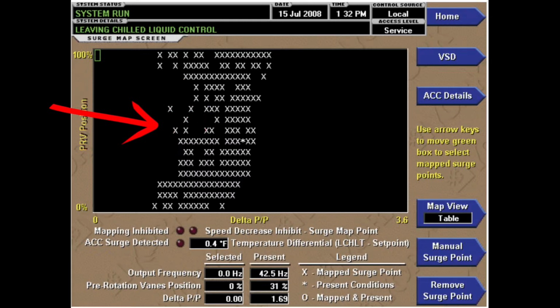Basically what happens is every time a surge happens, it compares the delta P to the PRV, the pre-rotation vane, the guide vanes, where that is on this graph in correlation, and then it will map that point. It wants to know that if I have this PRV position with this ratio, then I don't want to operate at that point any longer than I have to. So it will do its best to intentionally skip that area where the PRV and delta P correlate, so that you can prevent a surge. That's the whole purpose of this, to prevent a surge. So that is your delta P over P with a York YK centrifugal.